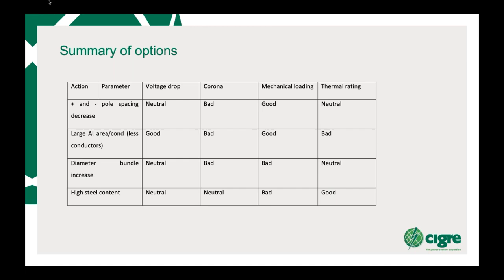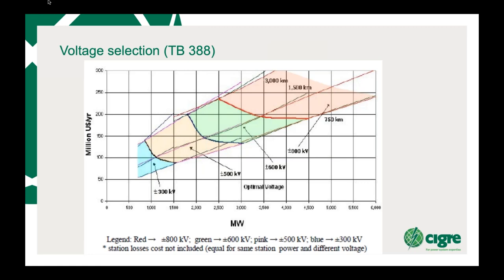Now, this is a graph which is found in TB388, and it's extremely useful to determine the voltage that you need for a particular megawatt transfer for a particular distance. So the first, these three lines: 750 kilometers, 1500 kilometers, and 3000 kilometers. Note that for high voltage DC, the trend normally is for very long lines. You wouldn't use a DC necessarily for short lines. And the left axis is million dollars per year.